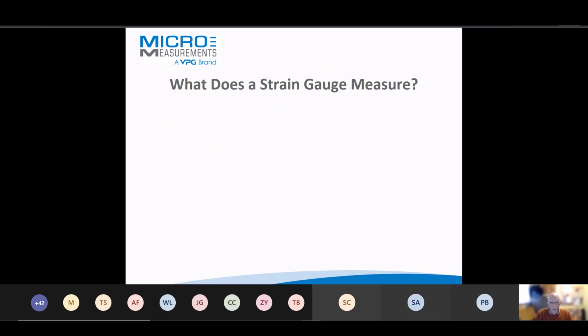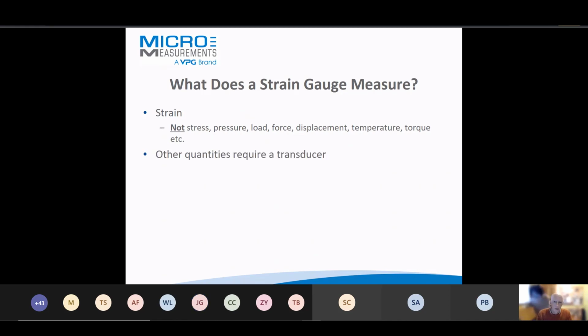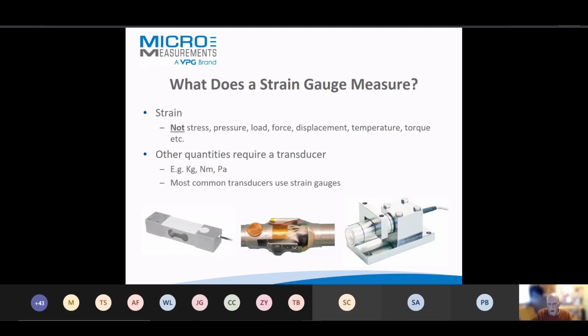So then the obvious question: what does a strain gauge measure? It measures, as the description says, strain - a simple answer to a simple question. But we get many questions about measuring other values with a strain gauge. A strain gauge cannot and does not measure stress, pressure, displacement, or the other things listed here. You may require a transducer if you want to measure pressure or load. If you're trying to measure kilos, you cannot buy a strain gauge to measure 20 kilos - you can, however, buy a load cell to measure 20 kilos that happens to use strain gauges.